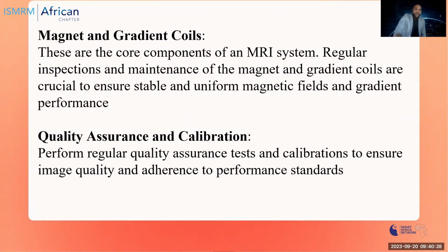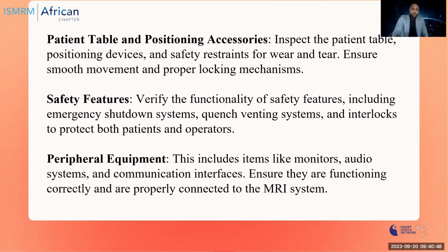The magnet itself has to be checked to ensure that the field is in line. Also, the coils must be checked and cleaned. The gradient coils too must be checked for any strange object around the gradient coil. Quality assurance, as I've mentioned earlier, also must be done.